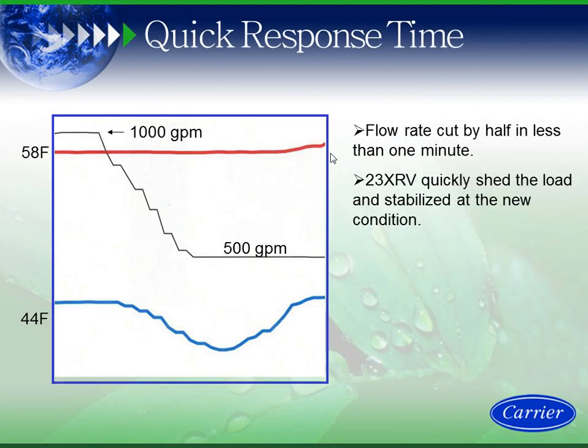This shows you how fast we have an 80% rate of change of flow on the 23XRV. Typical centrifugals are anywhere from 30%, for machines without electronic expansion valves. Machines with an electronic expansion valve, meaning machines with magnetic bearing compressors, have a 10% rate of change of flow. If you've had one out in the marketplace and noticed they've been sensitive to flow, that's because they're only capable of about 10% rate of change of flow, whereas the Carrier 23XRV is able to handle 80% rate of change in flow. We're able to cut the flow in half on a machine. If you look at a parallel chiller plant, when I go from one machine to two machines, my flow splits in half. Once that flow is split in half, can my machine handle it and stay on the line?